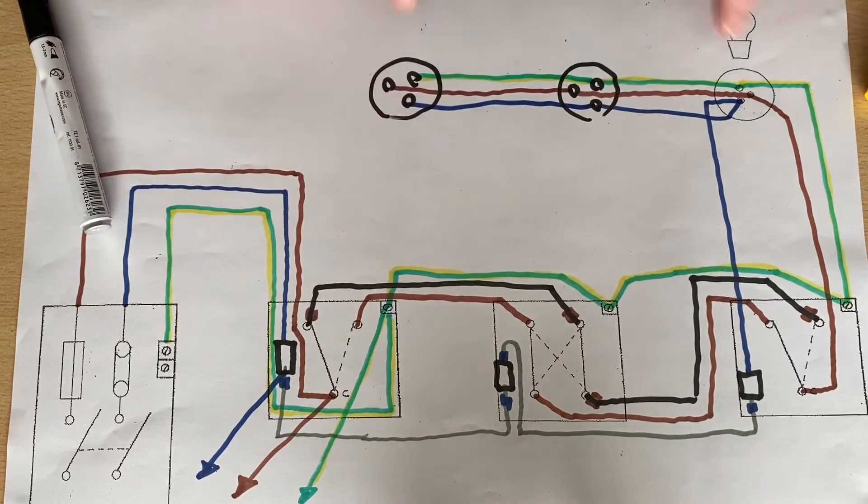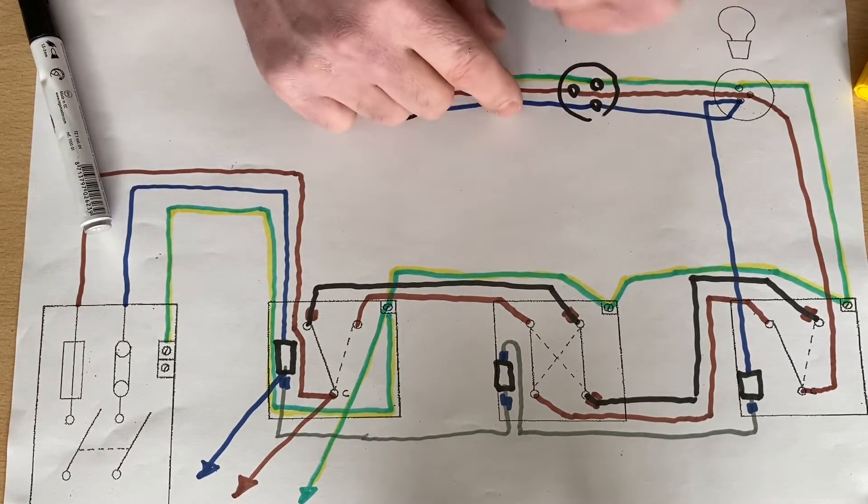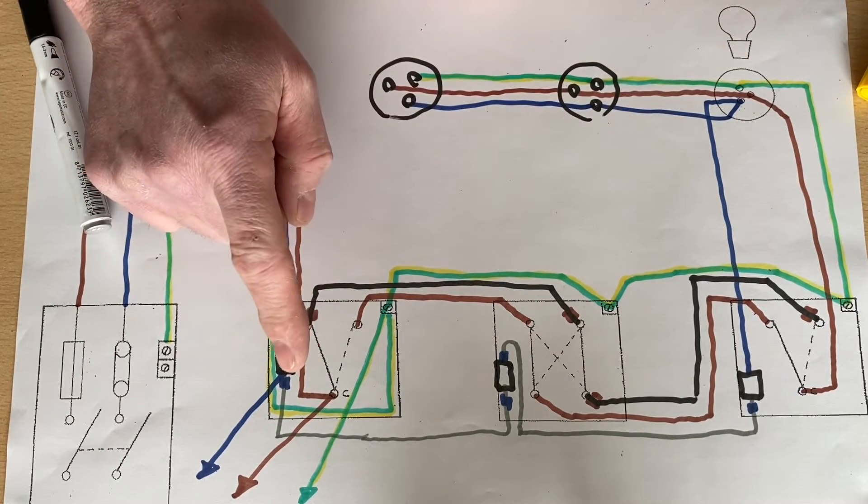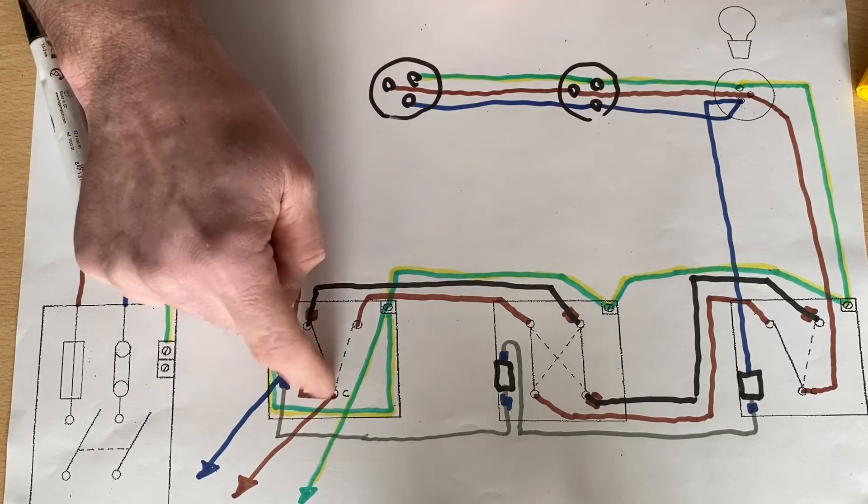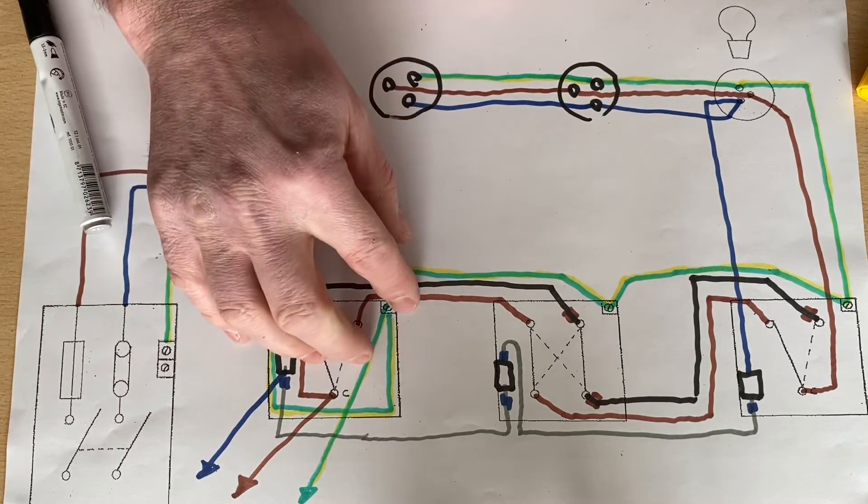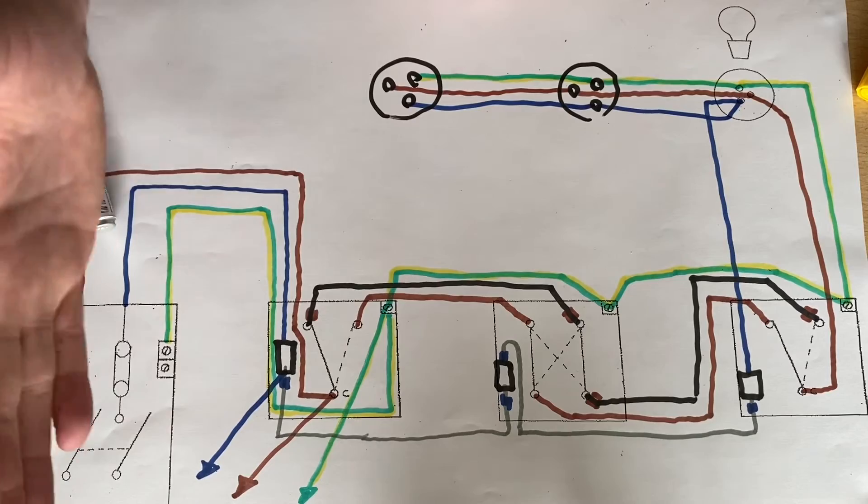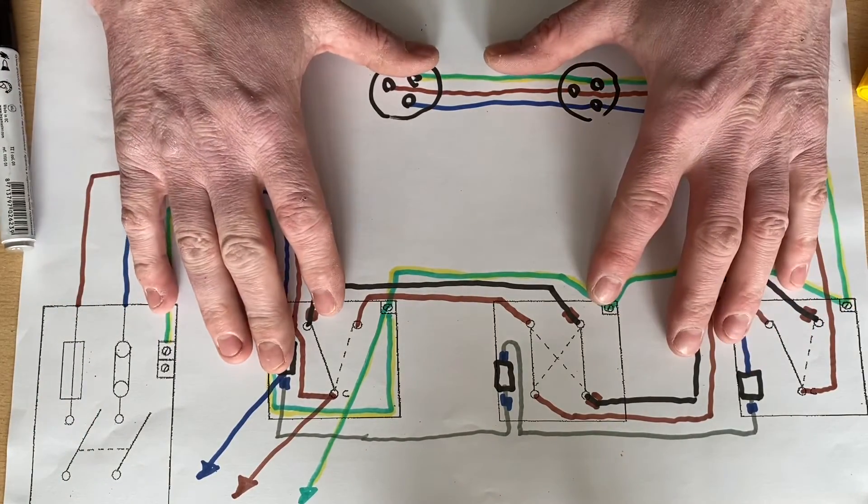So we bring it across and then we've got three down lights now connected to this switching sequence. We've got two-way and intermediate. In this case now we're controlling three lights. We've now worked out that we can take from our first two-way switch that has our permanent line, our neutral and the CPC, the supply over to the other area that you want to wire in using this method here.